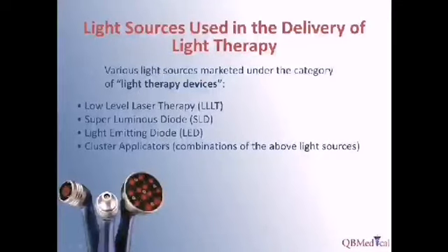These commonly include superluminous diodes, and light-emitting diodes, which may be in the same or similar wavelengths to a laser. However, they will not have as much penetration due to being non-collimated and or non-coherent. There are also cluster applicators available in some devices which will use a combination of laser, LED, and SLD.